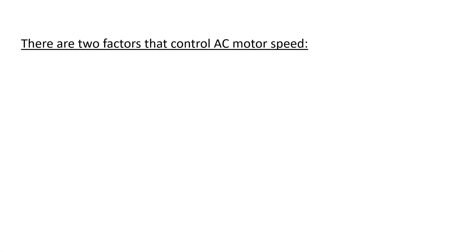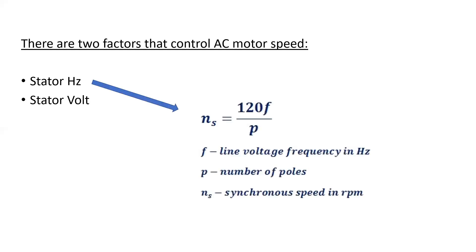There are two factors that control AC motor speed when it's driving a load. The first one is stator hertz. The second is the stator voltage, or the line voltage that's applied to a three-phase motor. Stator hertz is one that we can easily understand. Based on the synchronous speed calculation, we know the rotor is going to turn slightly slower than the synchronous speed based on the percent slip and the amount of load applied.